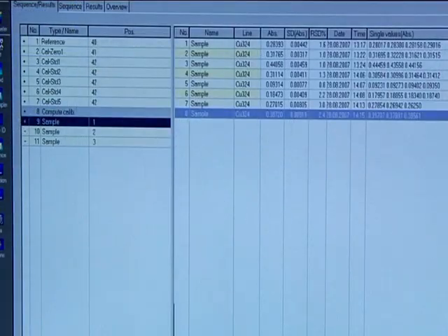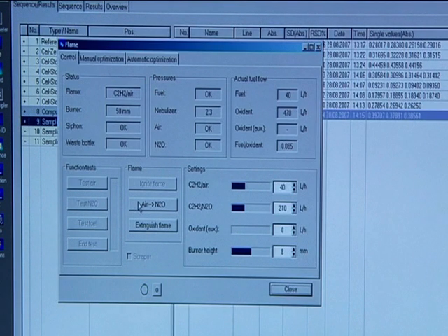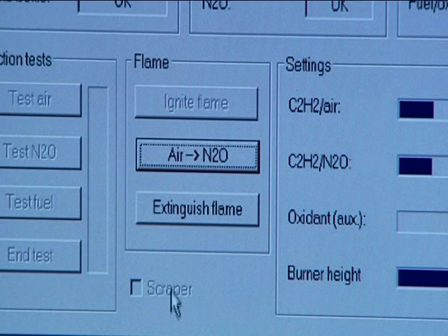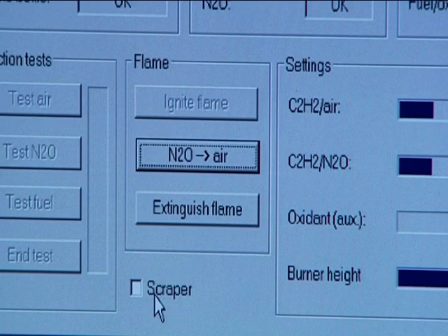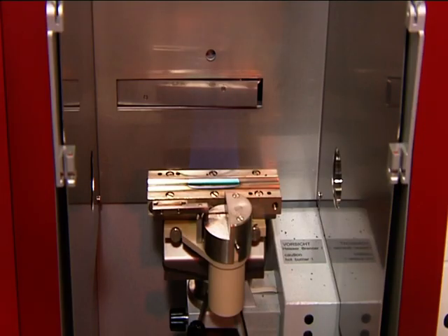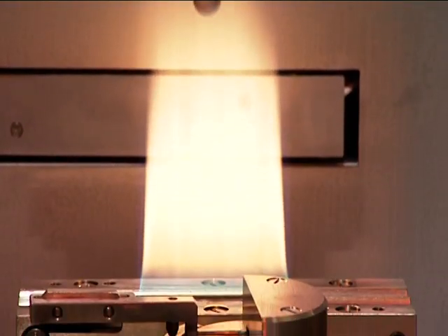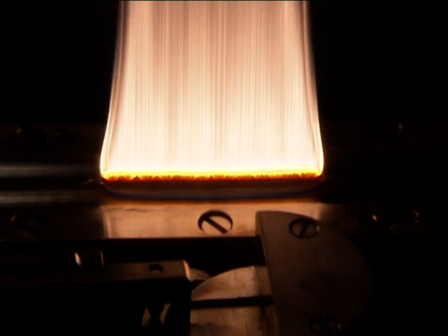As with simultaneous methods, the use of a single radiation source makes speedy analyses possible. By changing elements quickly, the ContraAA realizes a true multi-element routine. The well-thought-out self-check system guarantees trouble-free work. Sensors monitor all instrument components and provide security to the user during automated operation.